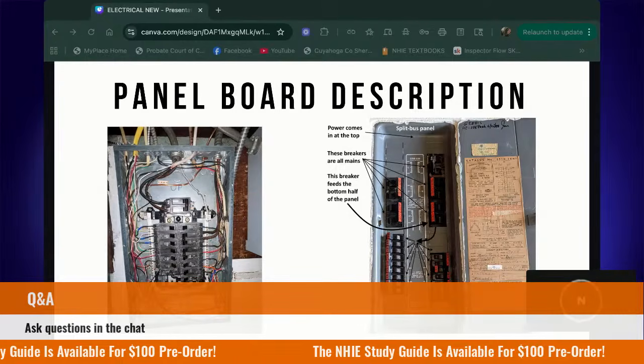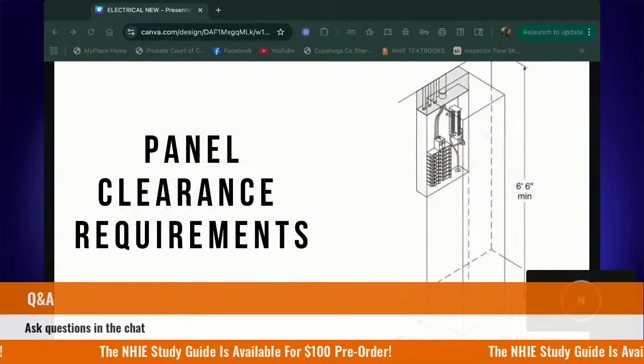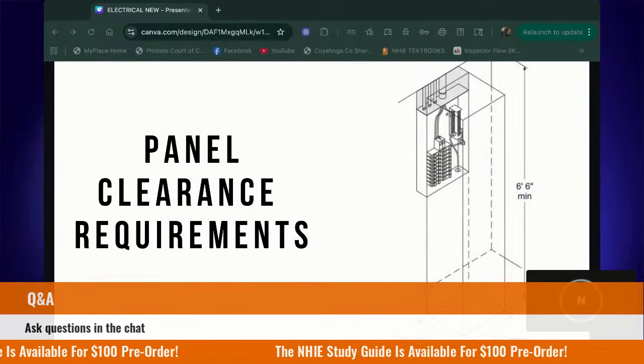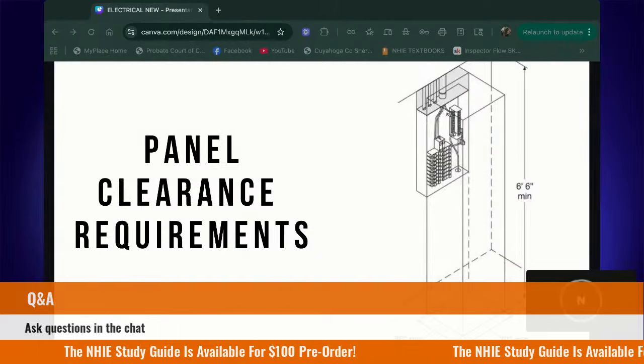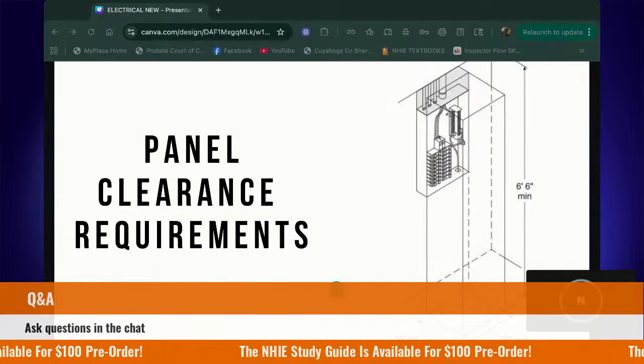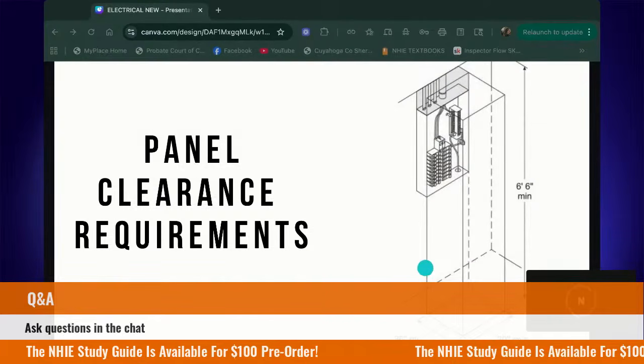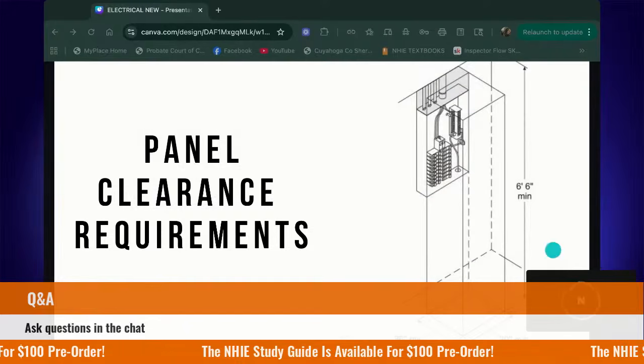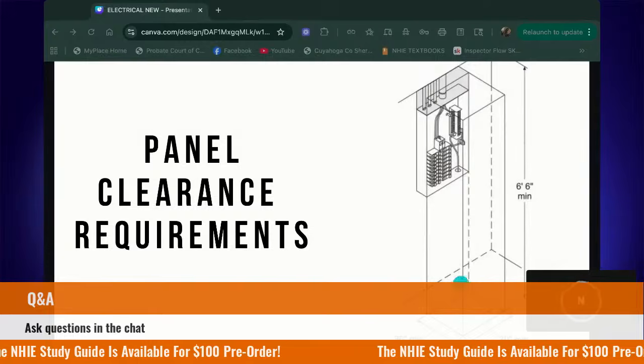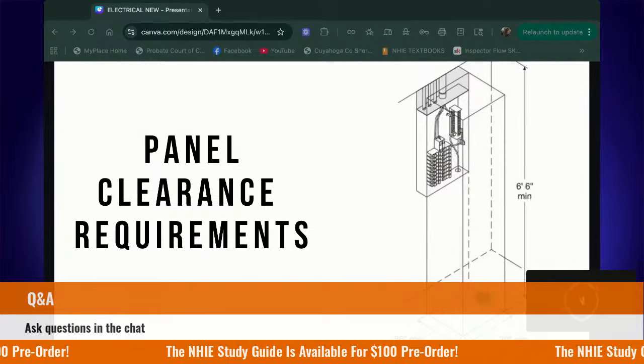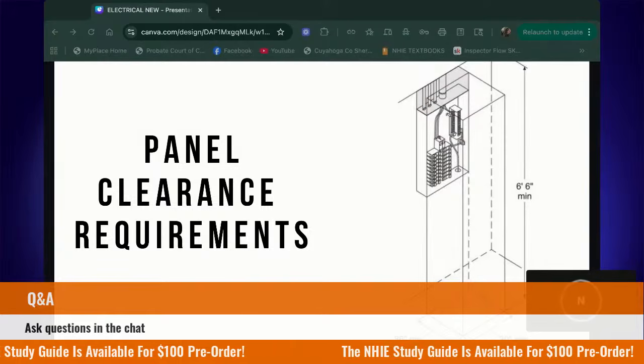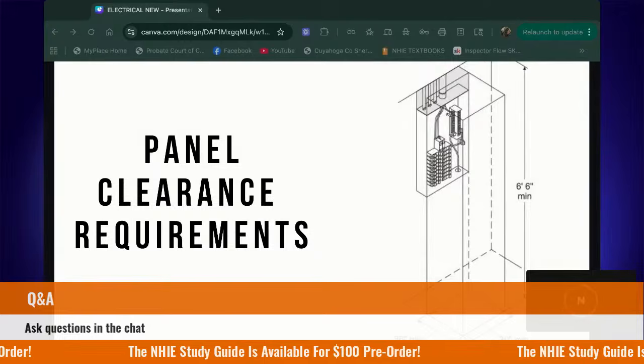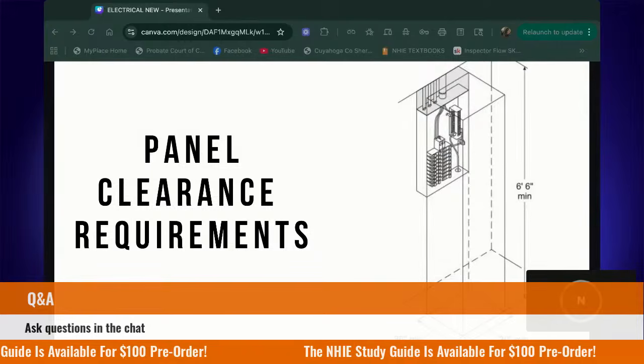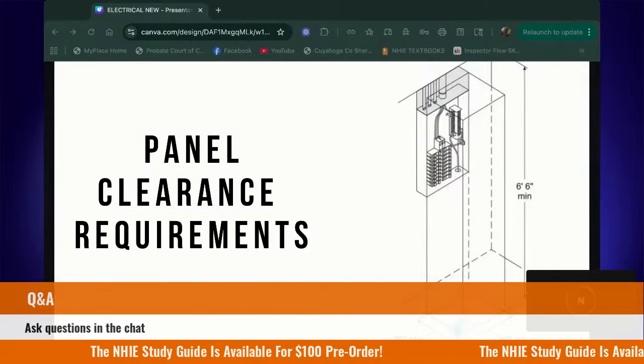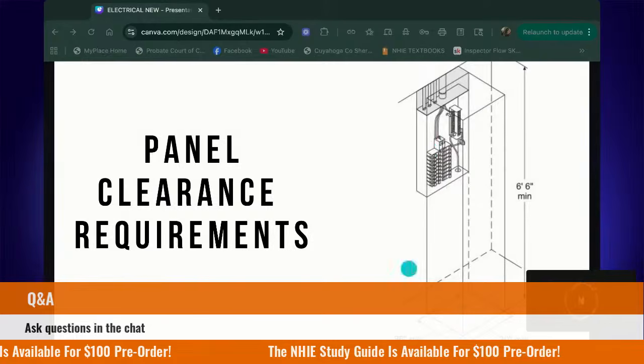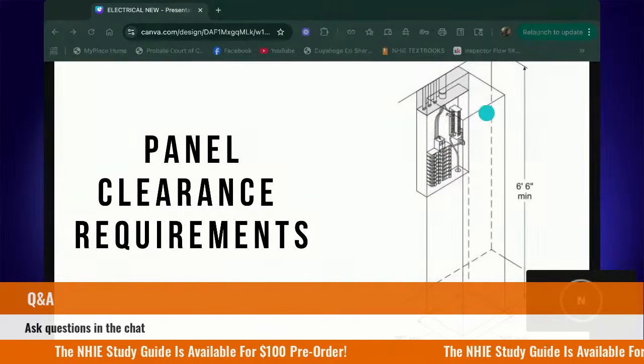Now, our panel clearance requirements for the actual panel itself. They want you to be able to actually access this panel for servicing and all of that kind of stuff. So again, these are code required. This diagram right here is straight out of the ICC. So these are code requirements. So your working space depth, a minimum of 36 inches clear space in front of the panel. So in front of the panel, there can't be anything else for 3 feet. Working space width, a minimum of 30 inches wide. As you can see here, headroom clearance, a minimum of 78 inches or 6'6".